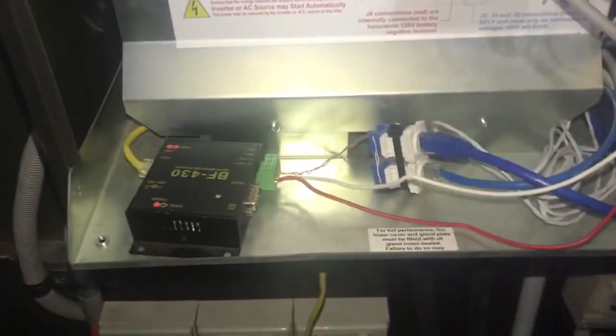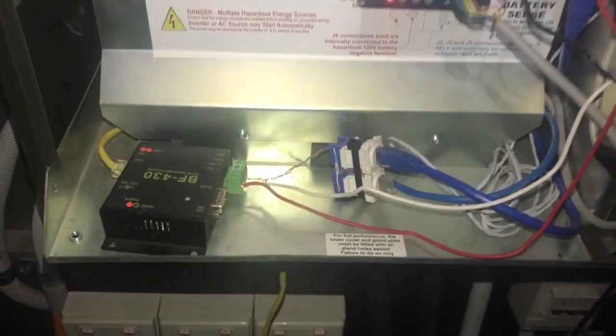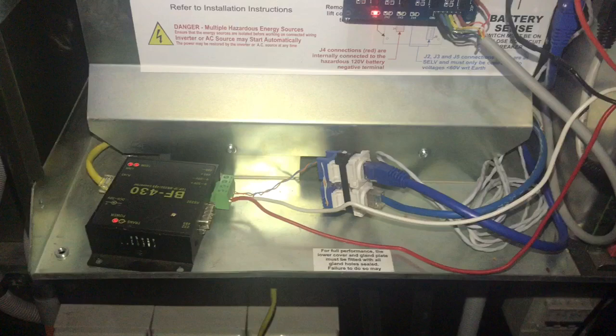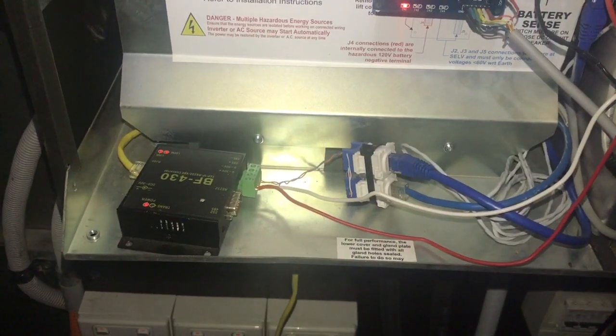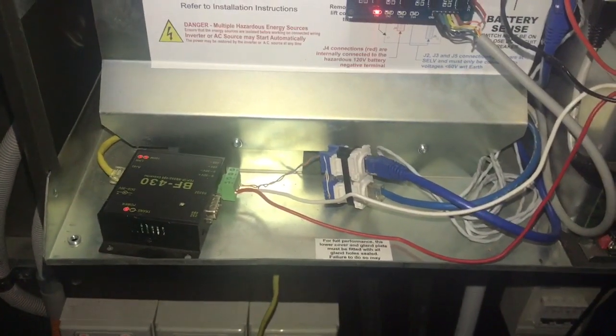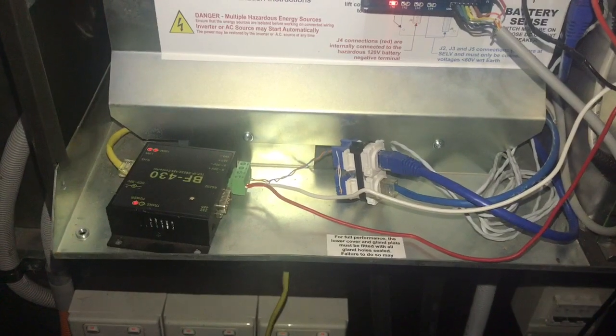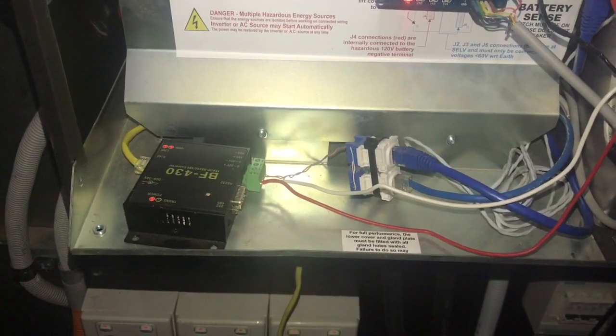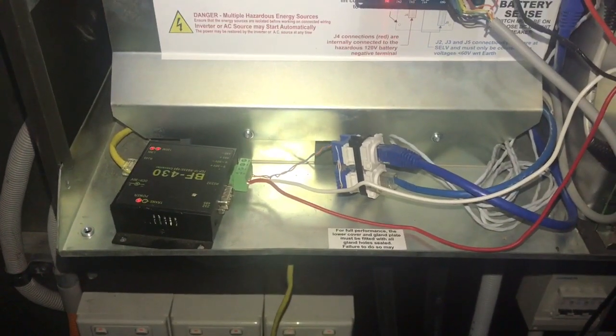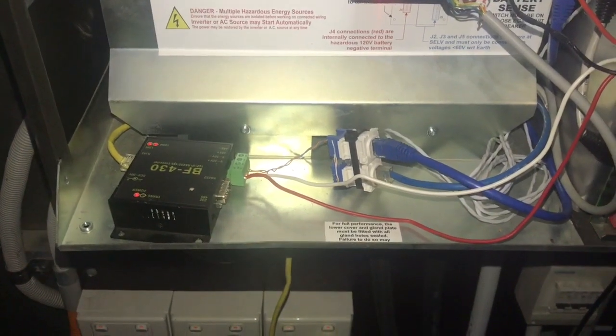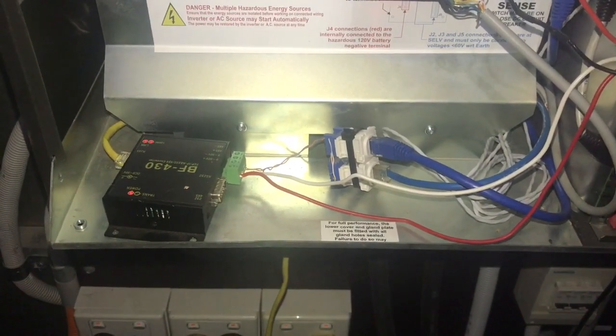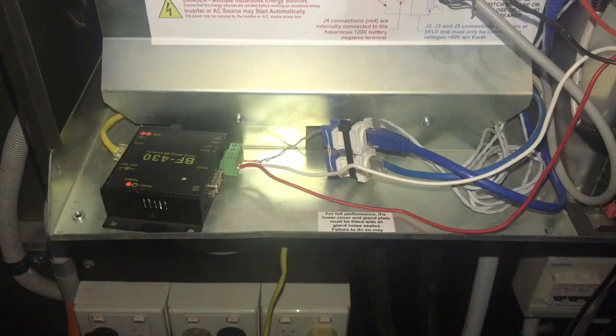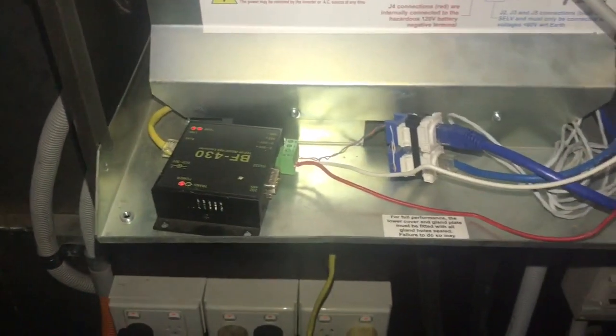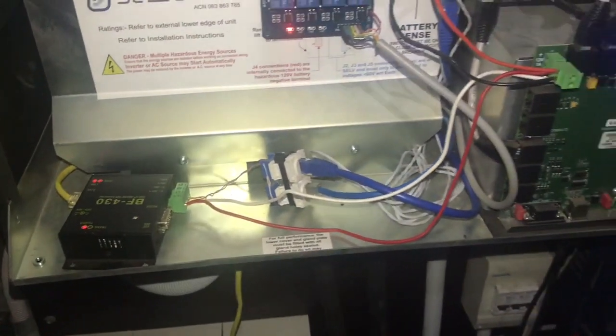This BF430 thing here is me extending things. We've also got an extra 5 kilowatts of panels on a roof further away on our property, and instead of an RS485 connection to the ABB inverters, we're using an IP connection to get down there, via an RS485 to IP converter.